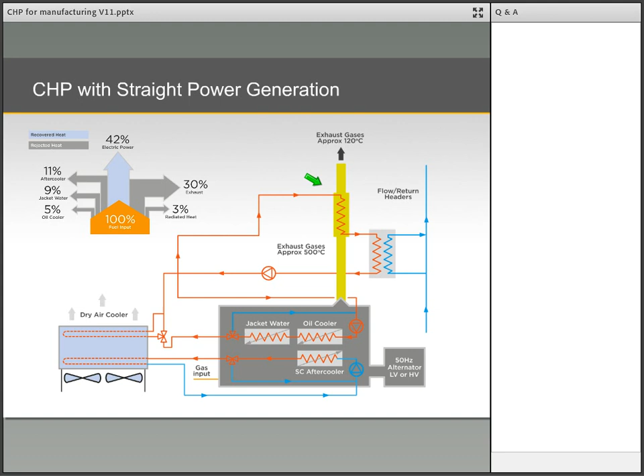The ideal scenario is always to be utilising the maximum possible amount of heat and power generated by the CHP, and this is by recovering all the heat as low temperature hot water from both the engine water jacket and the exhaust. The diagram on screen shows this scenario based on a single stage aftercooler system where only the engine water jacket and oil cooler heat is recovered, with the low grade heat from the aftercooler being rejected.